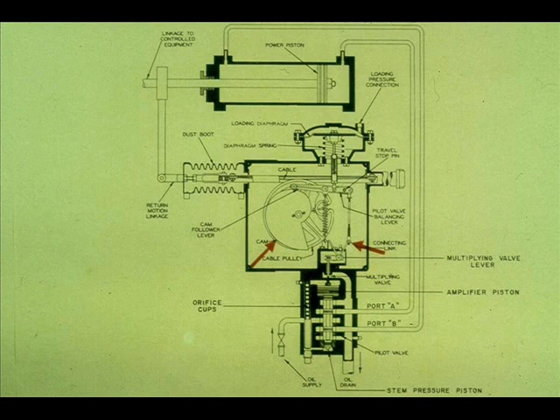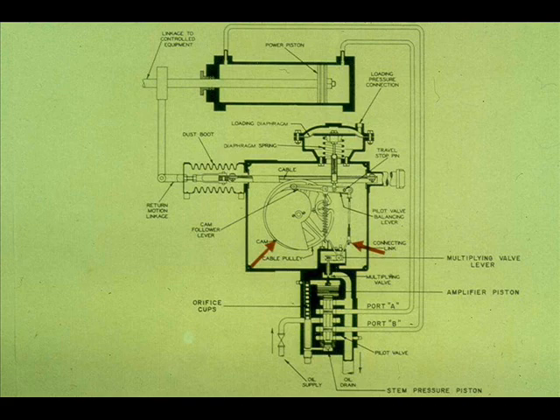The span of the power piston is controlled by the size and shape of the cam. The pilot valve setting, or zero adjustment, is determined by the pilot valve connecting link.